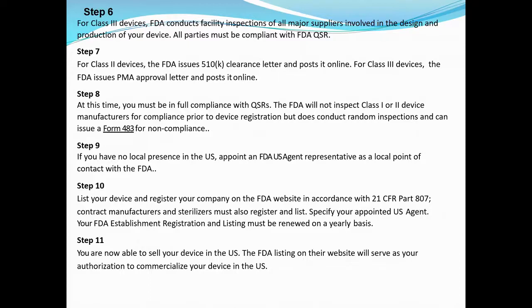Then for a class 2 device, the FDA issues a 510K clearance letter and posts it online. Similarly, once we get the approval, they post it on their website and we get that 510K number. And for class 3, the FDA issues a PMA approval letter and posts it online. PMA means pre-market approval.